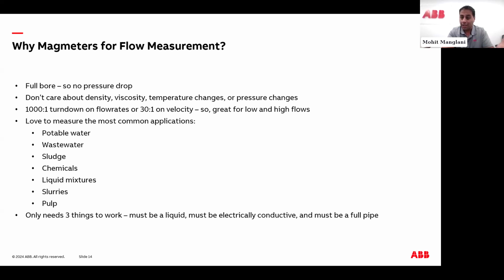I have a 10-inch line. I can put in a 10-inch mag meter, and depending on your velocity, more than likely it'll work very accurately. If you have changes in viscosity, density, temperature, or even pressure inside your process, as long as it's within the operating capabilities of the flow tube itself, the Schedule 40 piping with the flanges, a mag meter will work. 30-to-1 turndown on velocity. Like Raghu mentioned, I can do high flows up to 33 feet per second. I can even go down to 1 foot per second and still get an accurate reading.